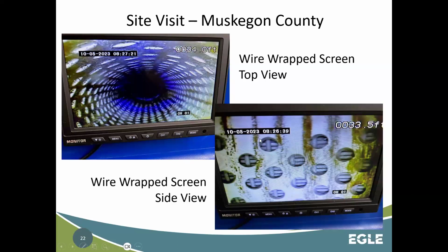Basically they take a piece of PVC casing, and as opposed to the slotted screen where they're just cutting the slots, they would drill holes in the casing, and then behind it they would wrap wire-round material. For this one, it's plastic. So these pieces would all be solvent welded together in a certain slot size.